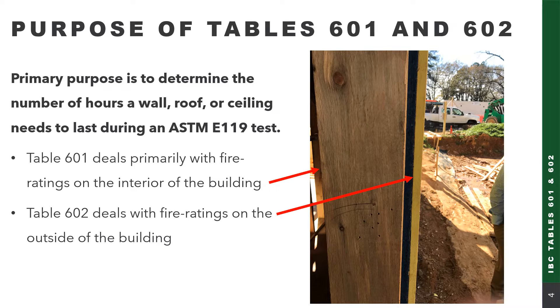The primary purpose of Table 601 and 602 is to determine the number of hours a wall, roof, or ceiling will need to last during an ASTM E119 test. Table 601 deals primarily with fire ratings on the interior of the building, whereas Table 602 deals with fire ratings on the outside of the building.